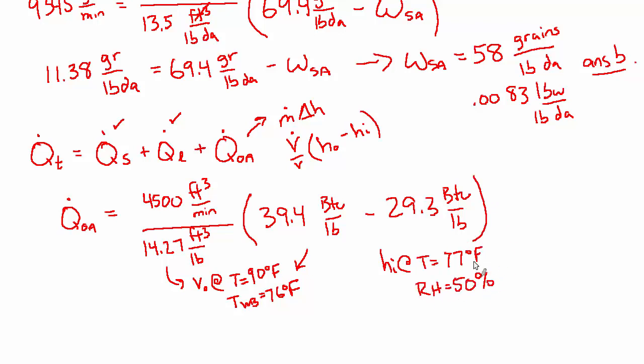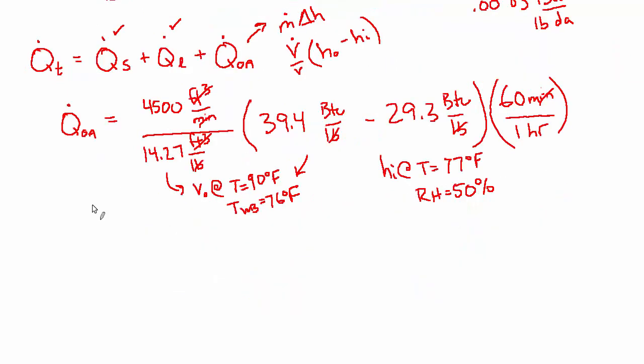T equals 77 degrees F and a relative humidity of 50%. And because these other numbers are going to be in BTUs per hour, this is currently on a per minute basis, so we'll just also multiply by 60 minutes for one hour. And the minutes will cancel, pounds will cancel, and the cubic feet will cancel. So we should end up with BTUs per hour. And that number is 191,100 BTUs per hour, which is a pretty significant contribution compared to the other numbers.